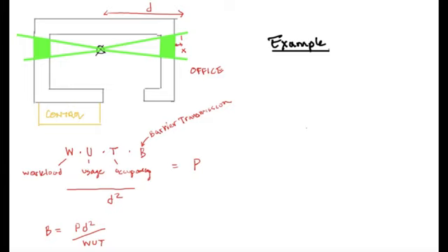So remember from last time, our goal, as I defined it, was to be less than 0.02 millisieverts per week. All right, and this is the goal for a public area, an uncontrolled area. So we're going to assume that this office is somebody who's not a radiation worker. So this is not a great design, but bear with me here.